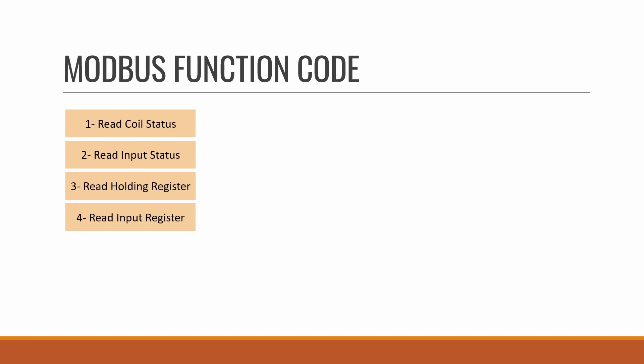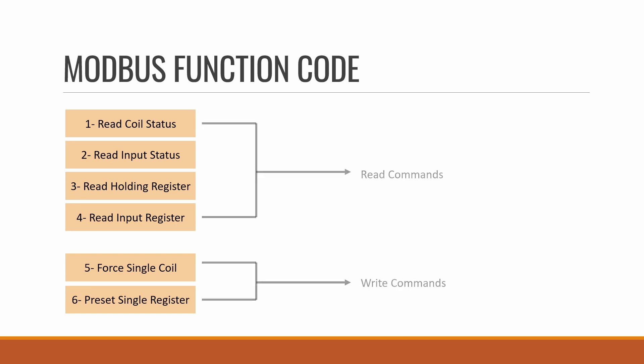Now, the Modbus function codes. Function codes are like commands used in Modbus communication. There are six Modbus function codes: the first four are reading commands and the last two are writing commands. Function code 1 is for read coil status, function code 2 for read input status, function code 3 to read holding register, and function code 4 to read input register. Function code 5 is for forcing a single coil, and function code 6 is to preset a single register.